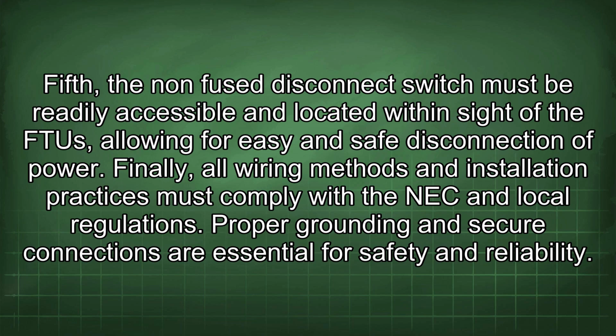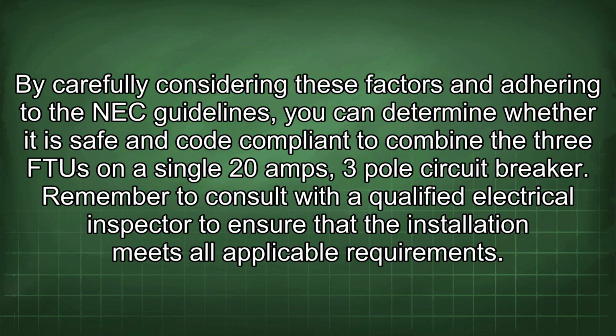allowing for easy and safe disconnection of power. Finally, all wiring methods and installation practices must comply with the NEC and local regulations. Proper grounding and secure connections are essential for safety and reliability. By carefully considering these factors and adhering to the NEC guidelines, you can determine whether it is safe and code compliant to combine the 3 FTU on a single 20 amp 3-pole circuit breaker.